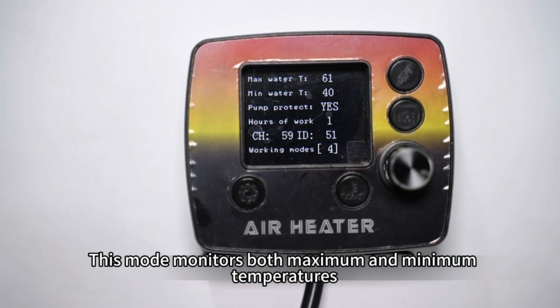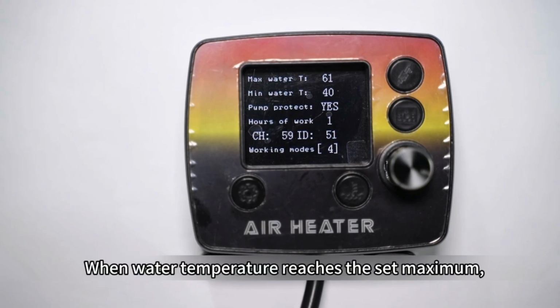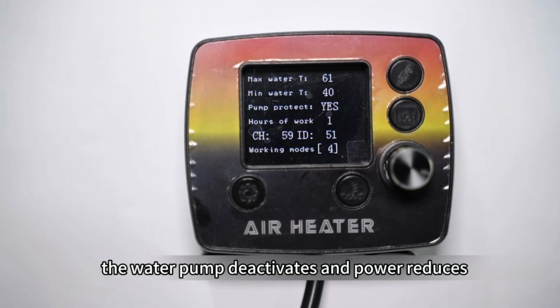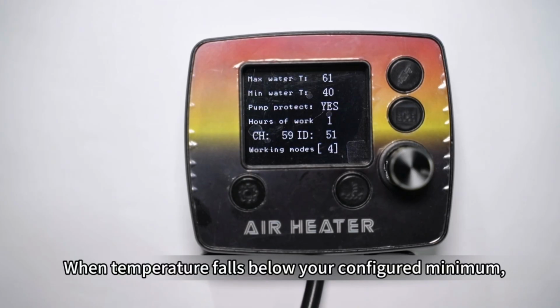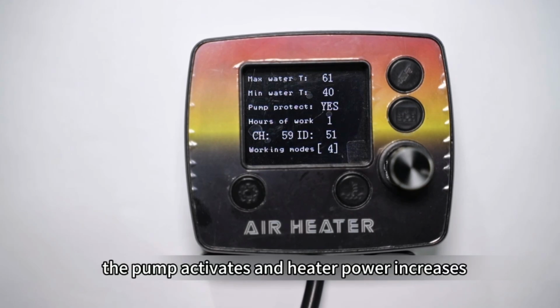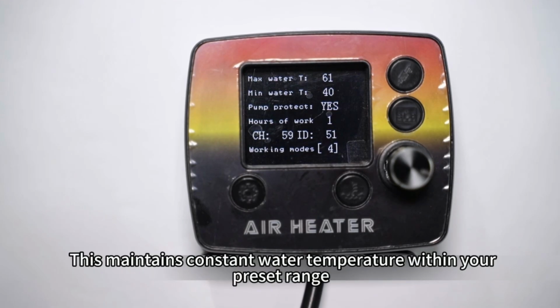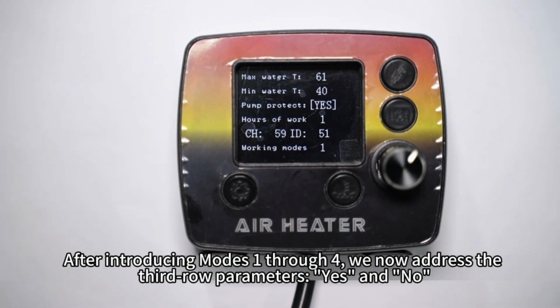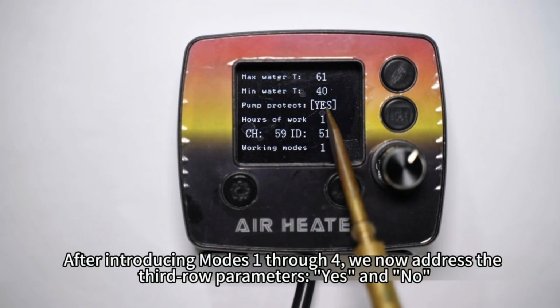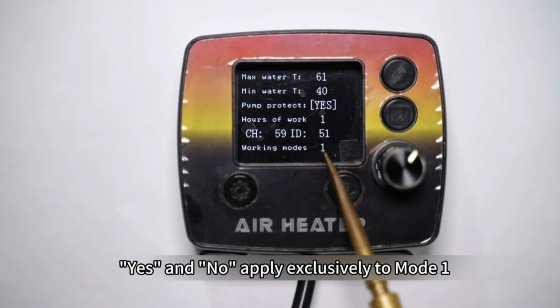This mode monitors both maximum and minimum temperatures. When water temperature reaches the set maximum, the water pump deactivates and power reduces. When temperature falls below your configured minimum, the pump activates and heater power increases. This maintains constant water temperature within your preset range. After introducing modes 1 through 4, we now address the third row parameters, yes and no. Yes and no apply exclusively to mode 1.